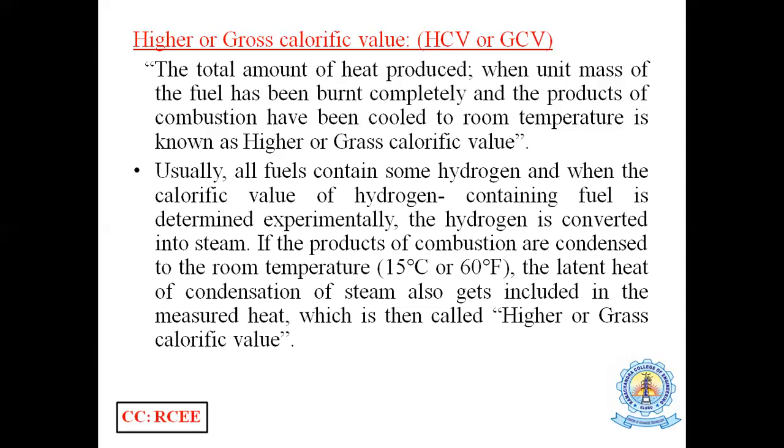That is why all fuels usually contain some hydrogen, and when the calorific value of a hydrogen-containing fuel is determined experimentally, the hydrogen is converted into steam. If the products of combustion are condensed to room temperature, like 15 degrees centigrade or 60 degrees Fahrenheit, the latent heat of condensation of steam also gets included in the measured heat, which is then called higher calorific value.